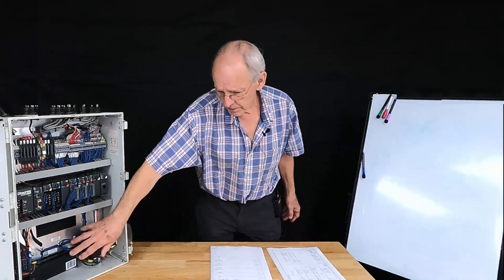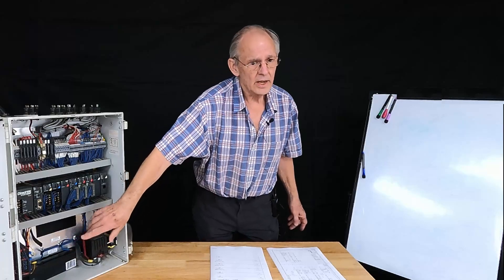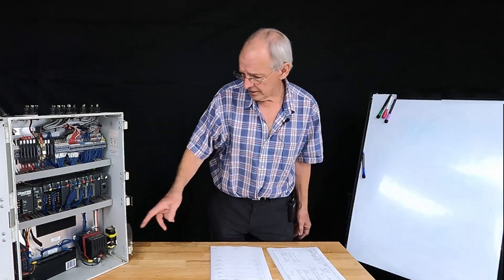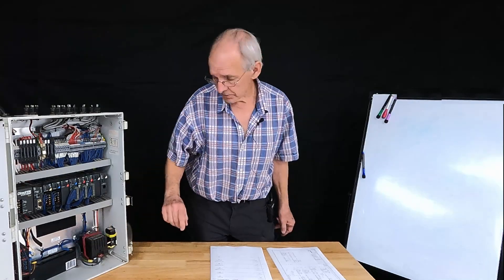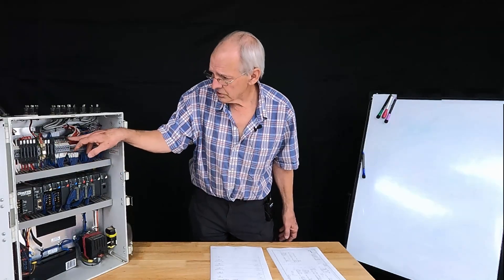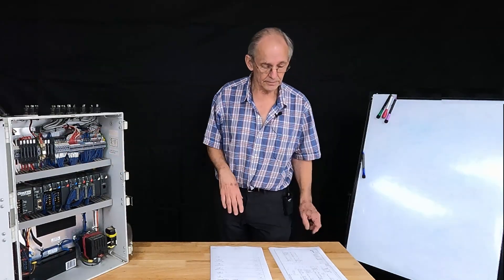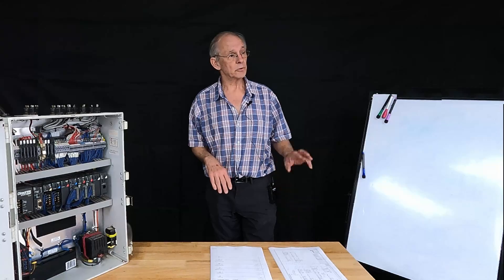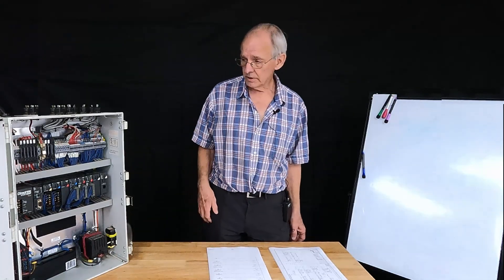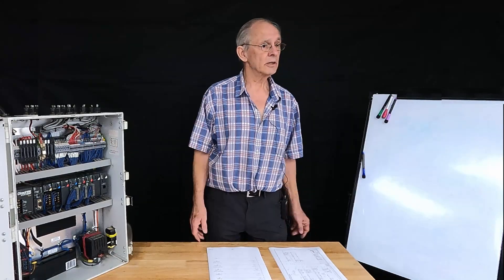And there's a battery that ran eight motor-actuated valves, and then the power supply charged the battery and some fusing. And in fact, there's Zener diodes that were done to slow down the valves. They were too fast. When the valves opened and closed, things slammed. So we reduced the voltage to the valves and got that to work.